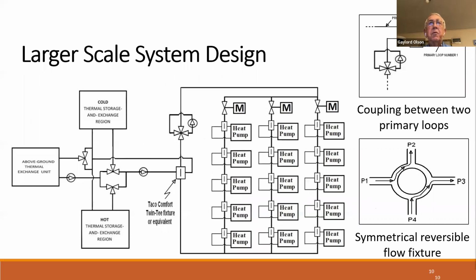You can kind of do a brute force way to get around this by using high flow rates and big diameter pipes. But rather than the brute force way, I would suggest that it might be better to periodically reverse the flow direction, maybe once per day or once per week. And so sometimes the bottom 3 heat pumps will have the best results, and other times the top 3 heat pumps will have the best results. And so over a long enough time, everybody has just the same average COP and average thermal capacity. Again, these are all water source heat pumps, and we have those Taco Comfort Twin T fixtures located at every single heat pump location.